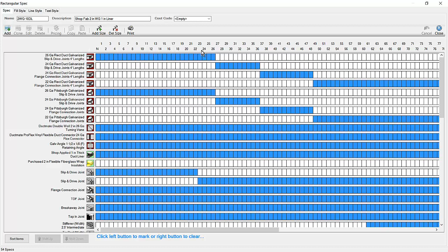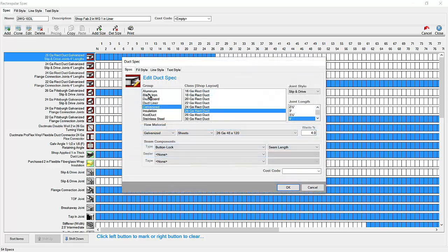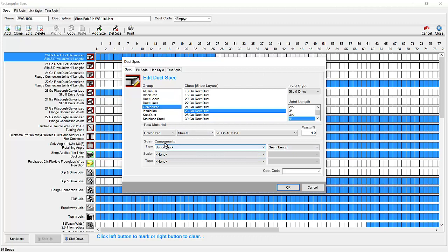Across the top is the greatest dimension. This is a rectangular duct spec. You can see the size range for each component in the spec. You can double click on a component to see more detail. This component is 26 gauge rectangular duct built in 4 foot joints. The joint type will be slip and drive, and the raw material used will be galvanized sheets.